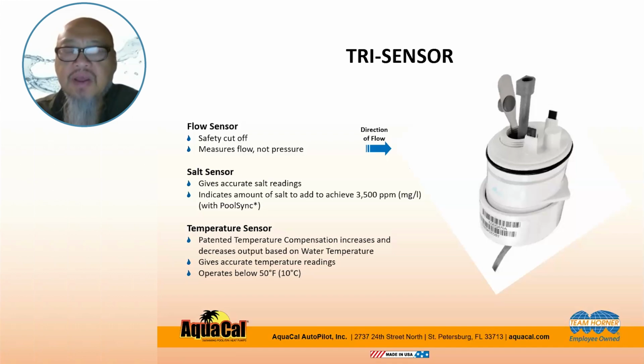But what happens when salt systems get to about 50, 55 degrees is all of our competitors will start shutting down their chlorine generation system. AutoPilot does not. We will continue operating below that 50-degree threshold. We do the temperature compensation to where the output is reduced, but we never shut off. Because one of the big things is, if you're selling a customer a salt system and you're charging them thousands of dollars for salt systems in most cases, why should you have to tell them that the water temperature is too cold and they have to supplement chlorine? With the AutoPilot, you don't have to do that. We will continue generating chlorine under those conditions.